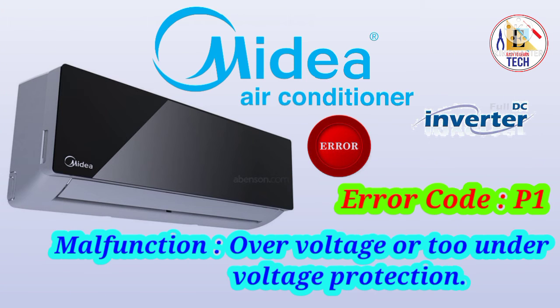When you see the error P1, it means over voltage or too under voltage protection for our outdoor unit system. When an outdoor unit is getting the voltage frequently less or high, at that time it will show the error P1. First of all, you have to check the main power supply, if the main power supply is giving proper power or not. If it is not giving proper power, then you have to make it stable, connect it and check.